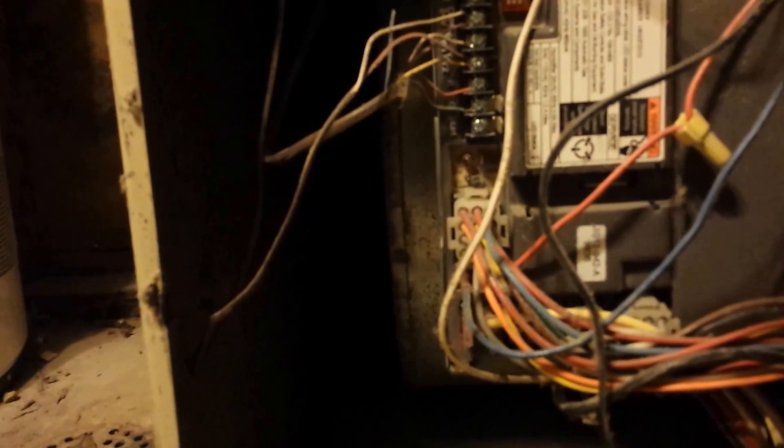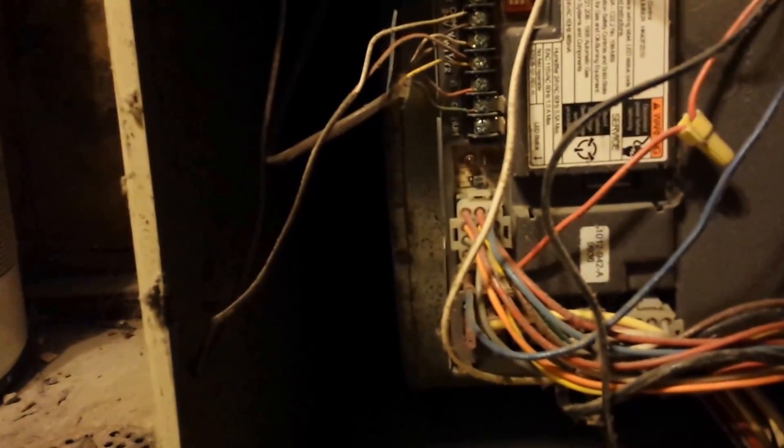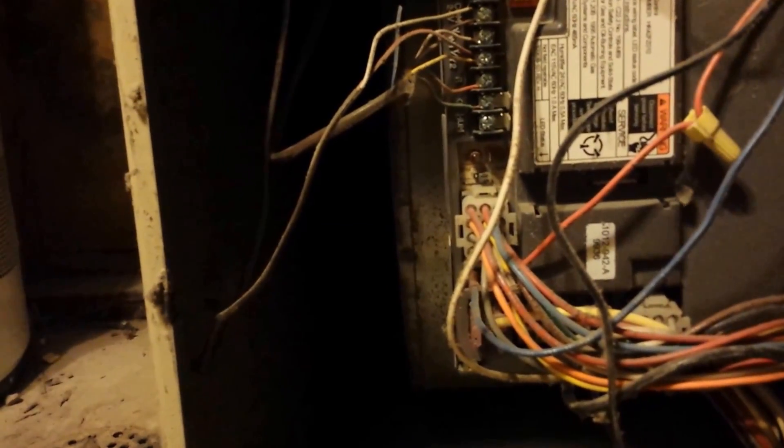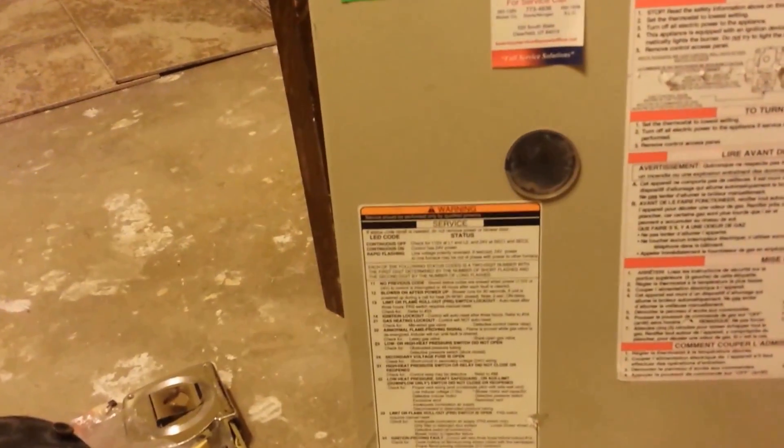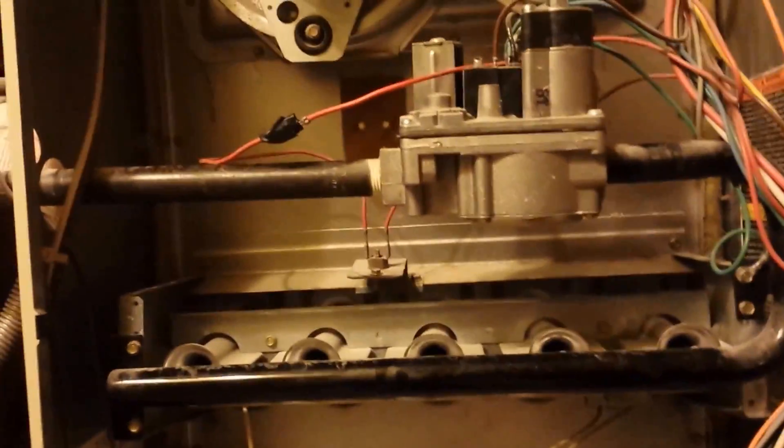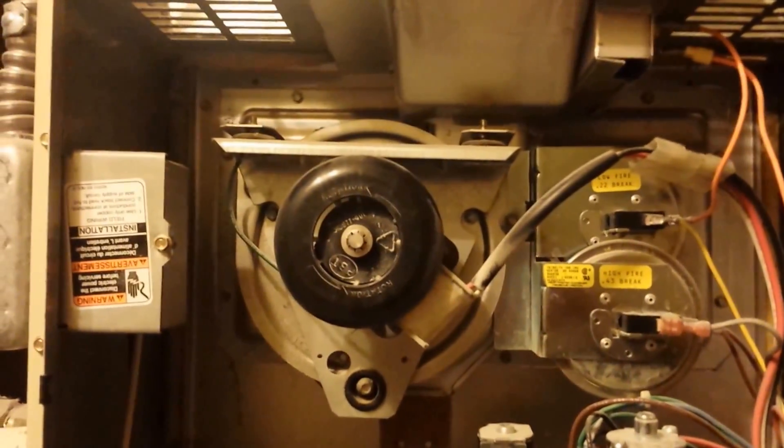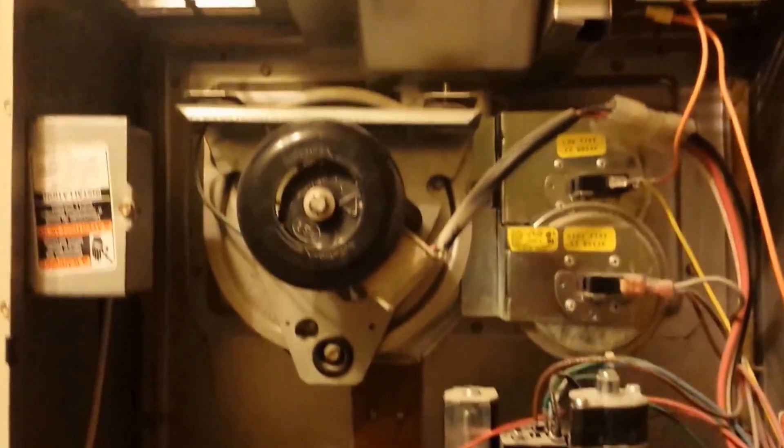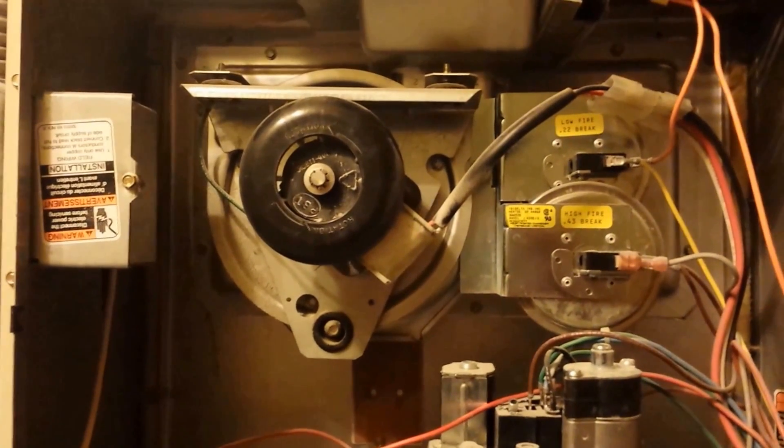Alright, so I taped those two together. And now I'm going to flip on the power switch. I'm going to depress this, and my red light comes on. Okay, so that just gave me error code 12. And error code 12 is that the blower is powering up after it's been off. And what should happen in about 30 seconds is this little exhaust fan will start spinning.